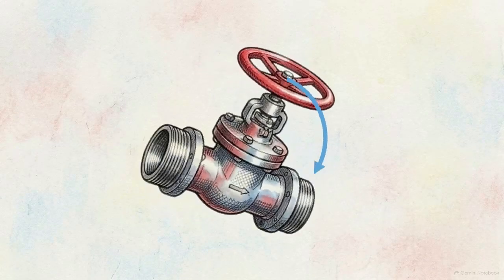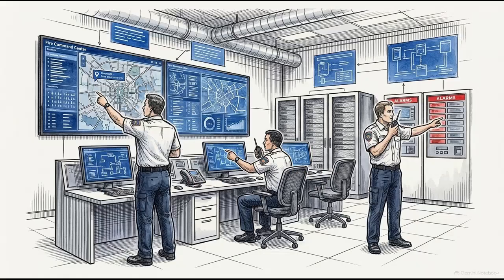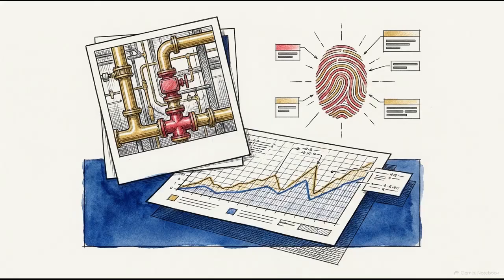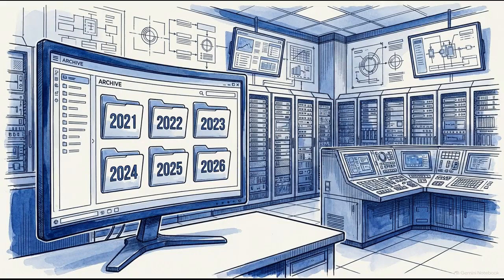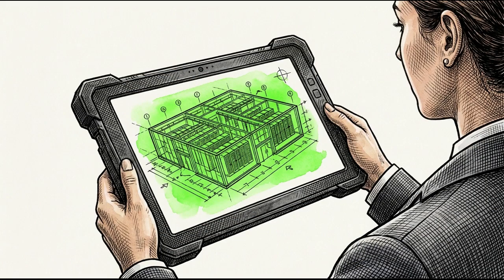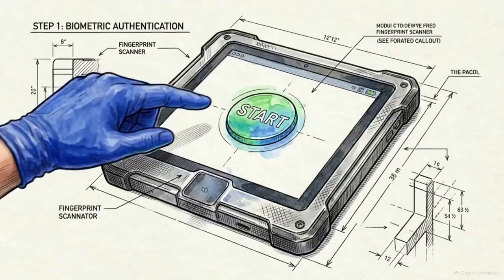A functional test confirms that a mechanical component works. An integrated exercise proves that the human organization can actually respond to a critical failure. Securing this response requires an audit-ready architecture. Every maintenance loop must end with locked evidence, including time-stamped photographs, raw telemetry, and named digital sign-offs. These records are moved into a document vault. Facilities must maintain 5 years of replicated data to ensure they can reconstruct their exact safety posture during an unannounced audit. The technician and the witness share the responsibility of logging as found and as left conditions, ensuring no discrepancy remains in the system.